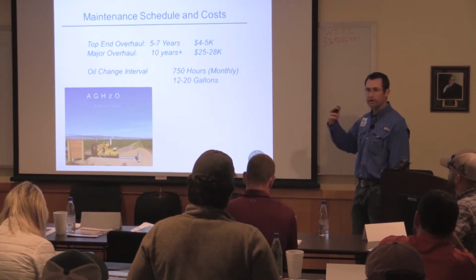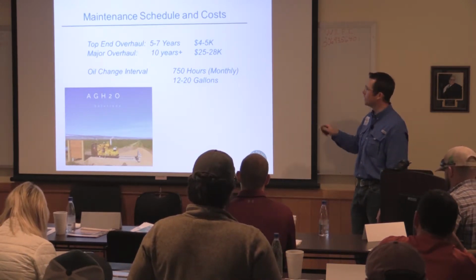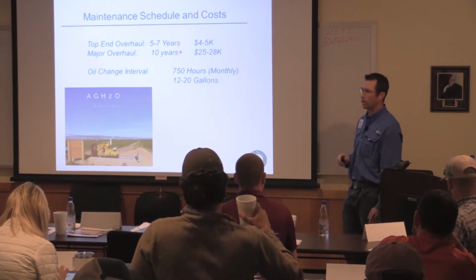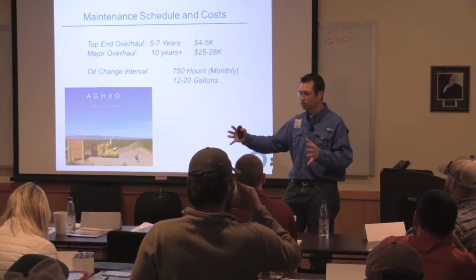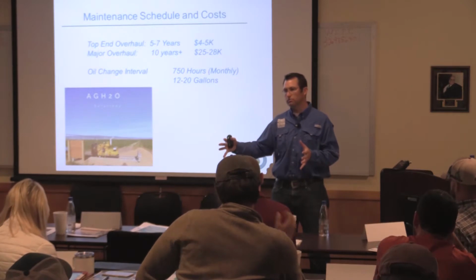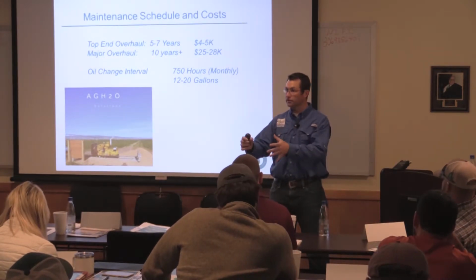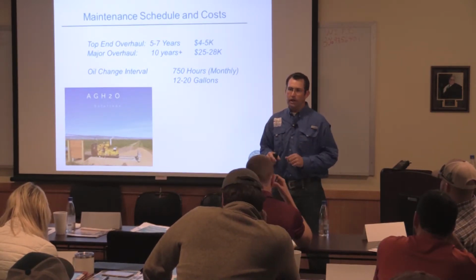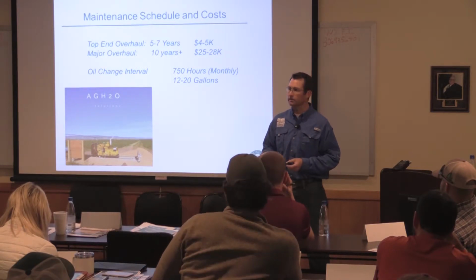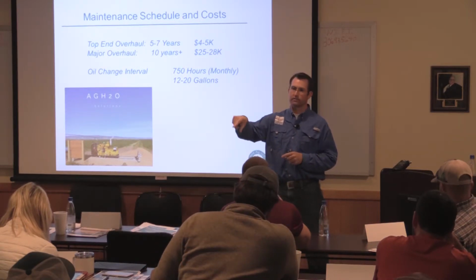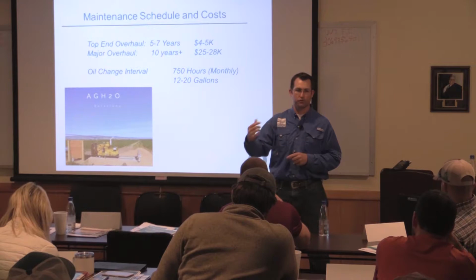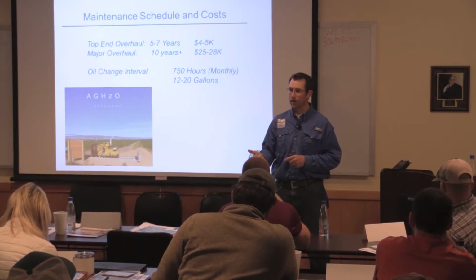Okay, so you start to add that into your maintenance costs. One thing I'd note on this maintenance cost and schedule that's hard to quantify: when you go from multiple natural gas motors down to one natural gas genset and multiple electrical motors, you find tremendous savings in not going from site to site changing oil on 4 or 5 motors versus one. Same with keeping up with oil, spark plugs, and tune-ups.